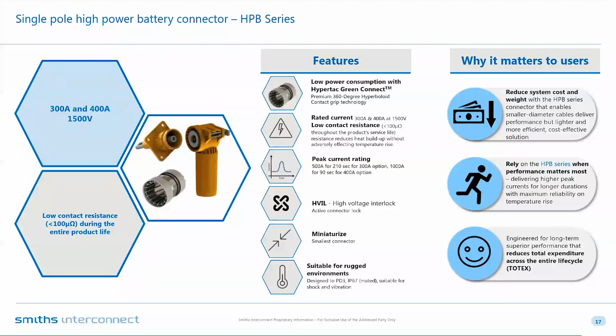The rated current is 300 and 400 amps at 1500 volts. But as I said, very few people talk about the lower contact resistance, because it's all good to say you have a high current connector, but the question is how low is your contact resistance—not just on day one, as shown in an earlier slide, but how low it remains throughout the product's service life, reducing heat buildup without adversely affecting temperature rise.